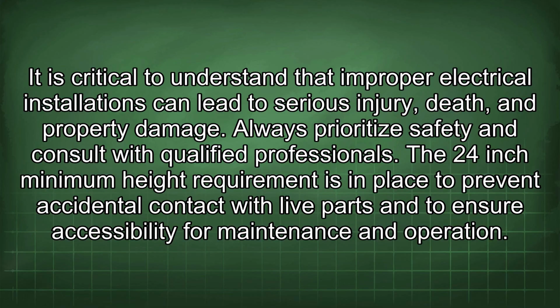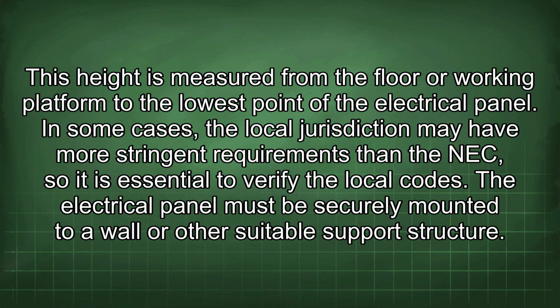The 24-inch minimum height requirement is in place to prevent accidental contact with live parts and to ensure accessibility for maintenance and operation. This height is measured from the floor or working platform to the lowest point of the electrical panel. In some cases, the local jurisdiction may have more stringent requirements than the NEC, so it is essential to verify the local codes. The electrical panel must be securely mounted to a wall or other suitable support structure.